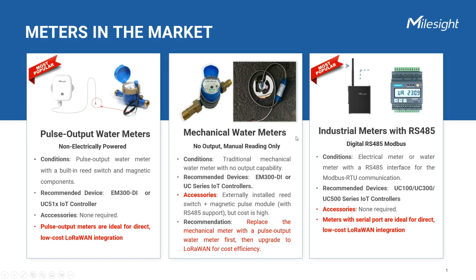Sometimes you may have traditional mechanical water meters. These old-school meters don't have any digital output at all - you're stuck reading numbers manually. Technically, you could add a pricey external module with a reed switch and magnetic pulse, and connect it to a UC controller. But honestly, it's cheaper to replace the meter first with a pulse output version, then upgrade to LoRaWAN. Save cash, skip the headache.